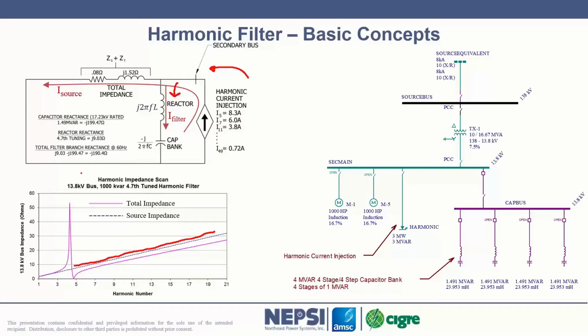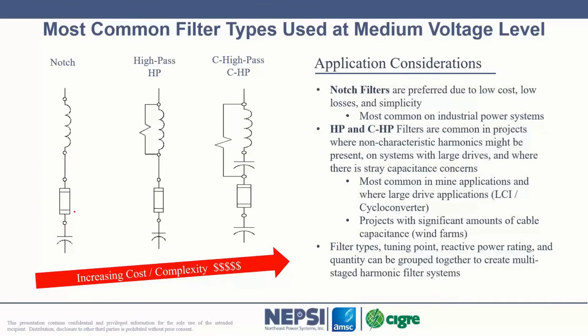We've reduced the impedance, except for at this location, which we refer to as an anti-resonant point, but it's basically a resonant point that exists below the filter tuning point. Whenever you put a filter onto a system, you have a low impedance point or a partially low impedance point, depending upon the type of filter, and you also have a resonant point that you must always be thinking about. Okay, what is the impact of that? So that's basically the basics of how a harmonic filter works. It offers a low impedance path to harmonics.